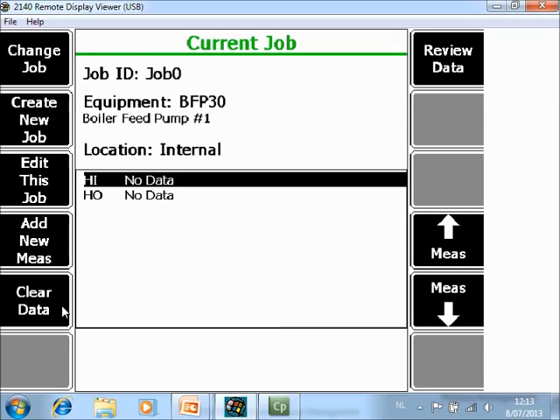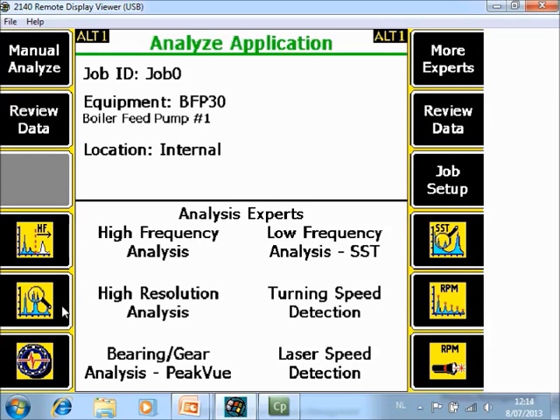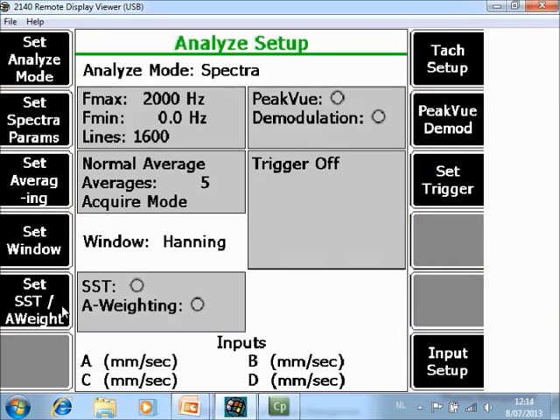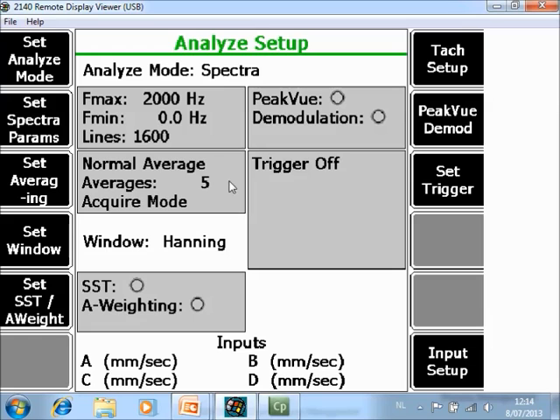Now we are ready to collect some data here. So I will start the machine. And I will go to manual analyze. I will measure from 0 to 2000 Hz, 1600 resolution lines with 5 averages. And I will measure only horizontal, vertical, and axial.